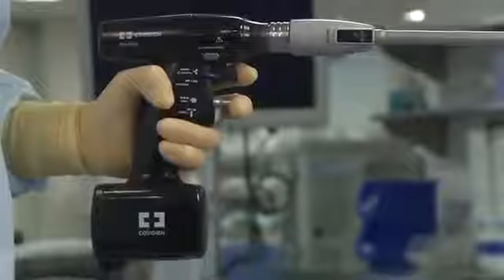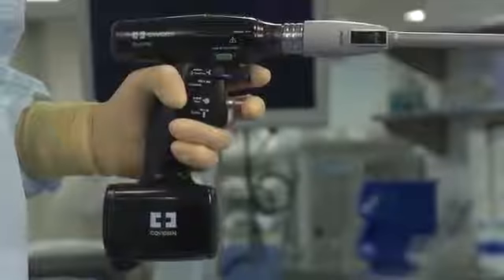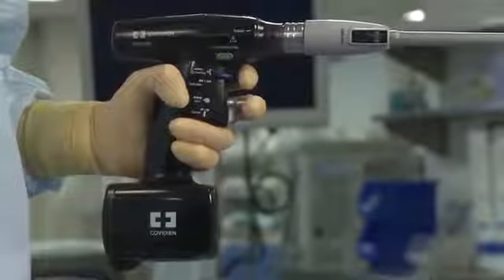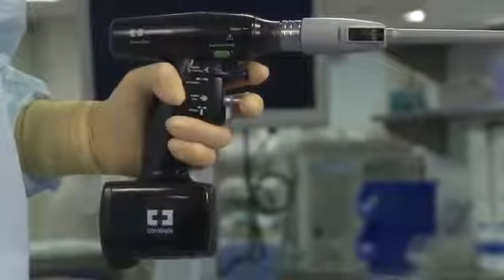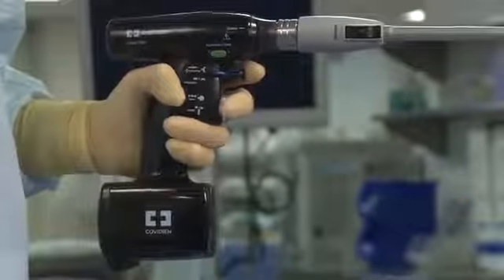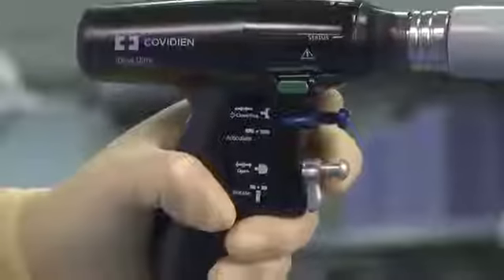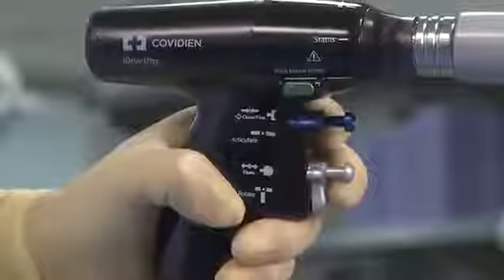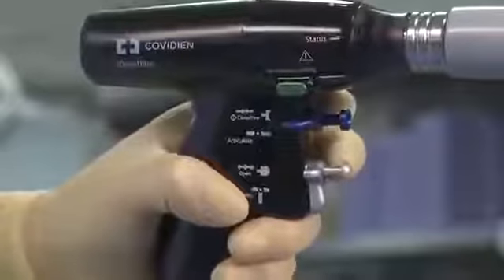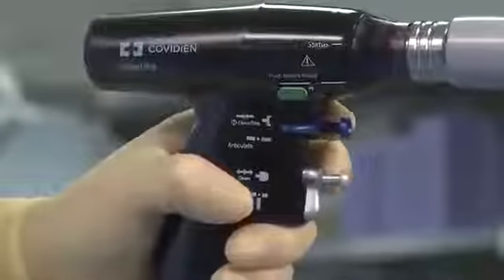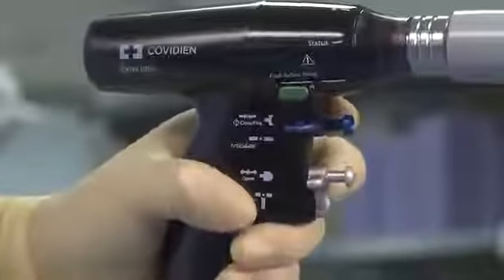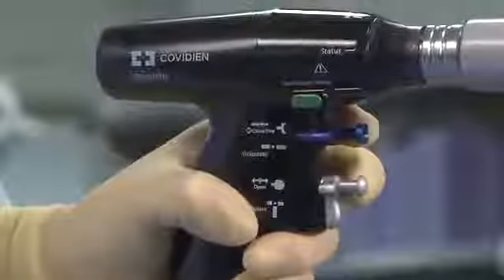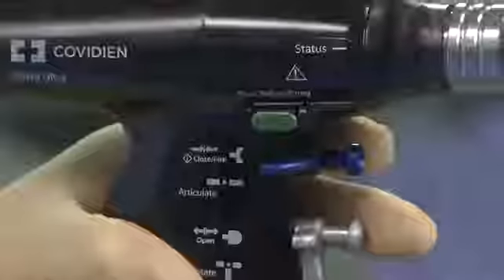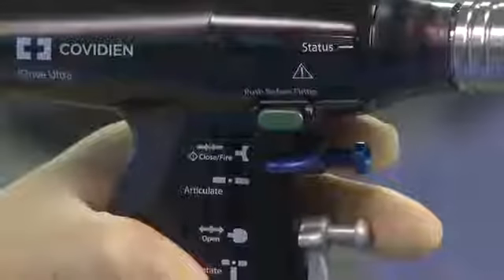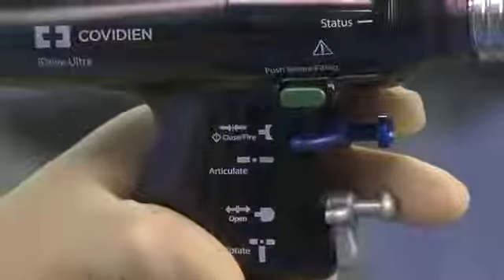The iDrive Ultra system features push-button operation. The blue push-button is used to close and fire the reload, while the silver push-button is used to retract and open the reload. The blue toggle can be actuated clockwise or counterclockwise to drive reload articulation as applicable. Likewise, the silver toggle is used to drive rotation of the Endo-GIA adapter and reload in either direction. 2 green firing mode buttons, one on each side of the handle, place the device into firing mode when either is pressed.